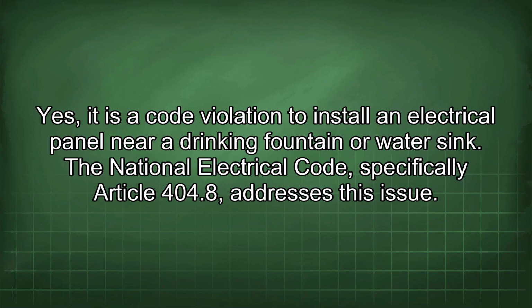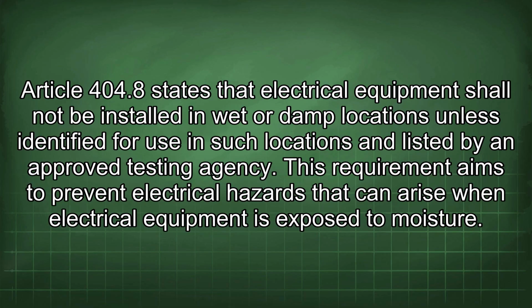Yes, it is a code violation to install an electrical panel near a drinking fountain or water sink. The National Electrical Code, specifically Article 404.8, addresses this issue. Article 404.8 states that electrical equipment shall not be installed in wet or damp locations unless identified for use in such locations and listed by an approved testing agency.